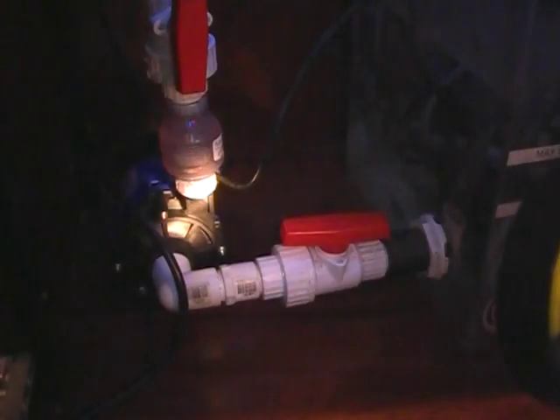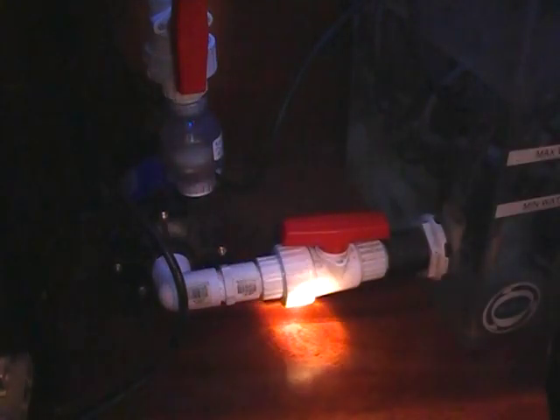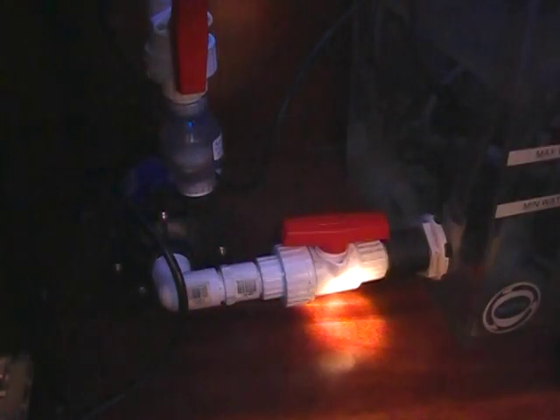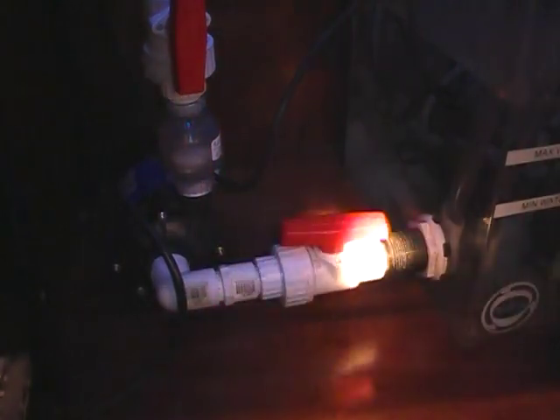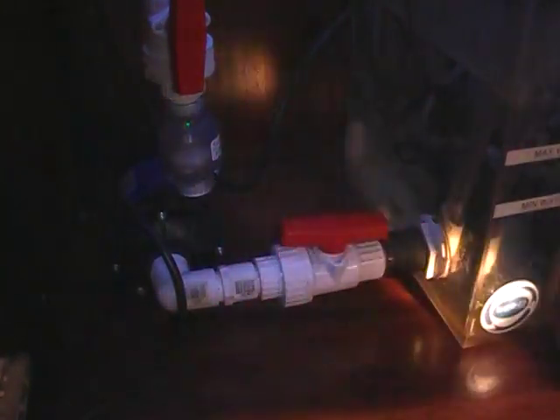That alarm is telling us the water temperature parameters are outside the settings the temperature controller has predetermined. We need to figure out what those parameters are, get the chiller running, and turn that alarm off. A quick check of all the plumbing items says it's working well, but I'm still concerned about that chiller, so I'm going to give the service fellow a call.